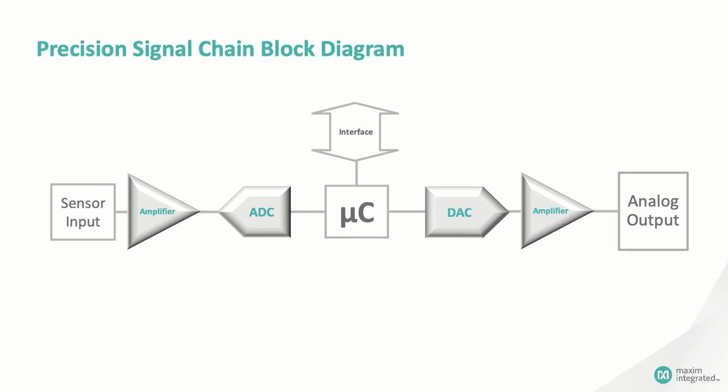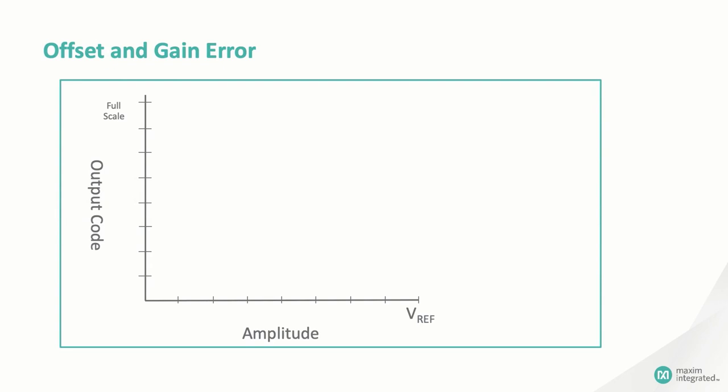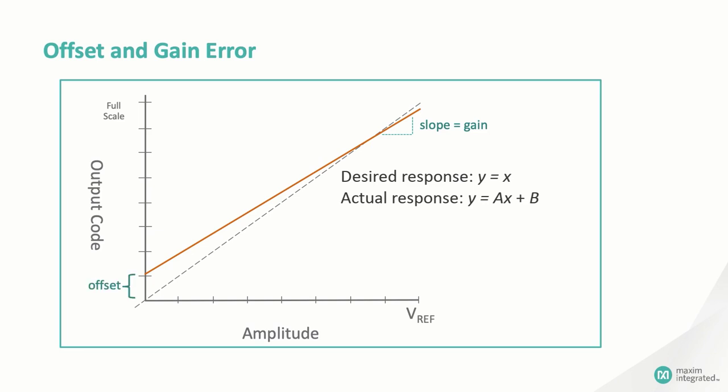That's not all. Don't forget that every data converter requires a reference, and those references just aren't perfect. They have a temperature coefficient and may themselves have an offset error. Here's the bottom line: what should be a perfectly linear y equals x relationship between the input of the signal chain to its output may well contain artifacts that contribute to an offset and a slope error, so that y equals ax plus b, where a is some non-unity slope and b is some non-zero offset.